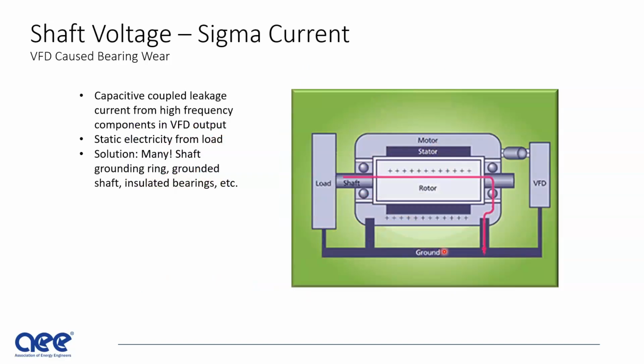Shaft voltage: when VFDs were initially used on motors, the high frequency components would transmit through the insulation to the grounded shaft, and that created a current to ground through the rotor. So the solution was grounding rings, a grounded shaft, or insulated bearings. All the motor manufacturers today have mitigating components or solutions for their motors. You just want to make sure that they're specified and stated in the specification. Marathon uses an Aegis shaft grounding, and Baldor uses a shaft grounding ring.